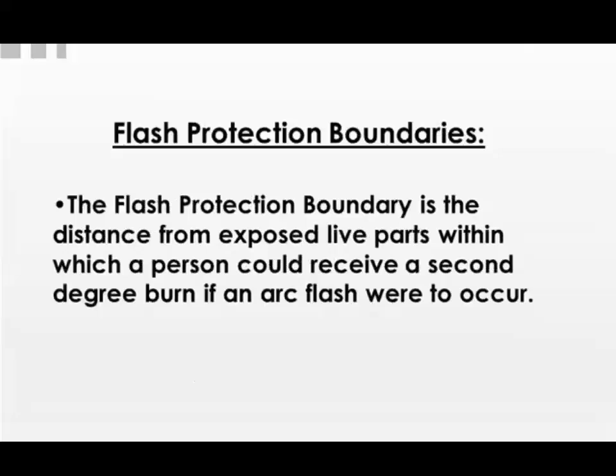Flash protection boundaries. Okay, the flash protection boundary is a distance from exposed live parts within which a person could receive a second-degree burn if an arc flash were to occur. That's an unprotected person. Now, this has recently changed. They've gone away from this, the second-degree burn, they've updated it recently, but a second-degree burn is still very serious. So a flash protection boundary is going to protect somebody that, if exposed, again, not having any arc flash personal protective equipment on, will still result in a second-degree burn. That's not saying they're not going to get burned. That's a key factor to understand. But it's going to save somebody's life.